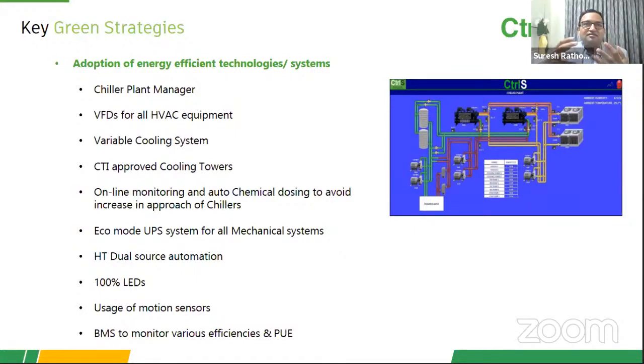Now, that avoids a lot of filtration itself. All UPS systems for mechanical load are on eco mode. Every PAHU machine has HT dual source automation. 100% lighting is on LED, with motion sensors so that LED light consumption is also on the lowest side. And the BMS monitors the PUE.